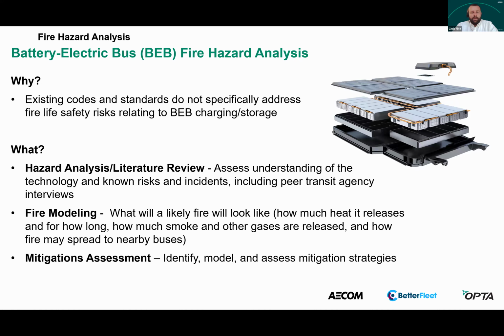So when starting any project, regardless of the scope, I always recommend performing a fire hazard analysis to evaluate how what we're planning on building or modifying will impact the employees, their operations, and facilities. An FHA is especially important when dealing with technologies that are developing as quickly as battery technologies, which we've seen have had documented failures. While our codes and standards writers are updating their documents based on the available information they have, the process does take time, and it doesn't always keep up with rapidly evolving technologies like we see with battery energy storage.